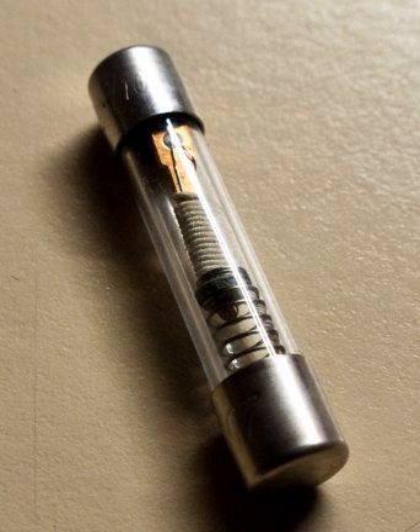When pulling or plugging HRC fuses over 63A, ARC-tested work clothing is recommended by the employer's liability insurance associations. An insulating mat and insulating gloves may be required. Improper pulling of an HRC fuse insert under load can result in an arcing fault which, without protective equipment, can result in serious to fatal injuries.